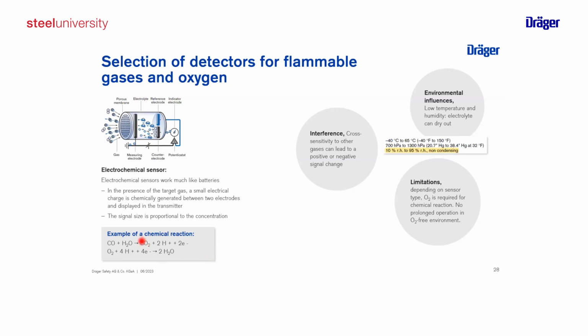I mentioned we also have some water inside, so liquid. So we need a certain environmental condition for the sensors so that they can operate. What we typically specify is 5 to 10% relative humidity as a minimum. Otherwise, the humidity from the inside will vaporize to the outside, so the sensor will dry out, and the electrons can't be generated or can't move through the electrolyte because there's nothing left. So you see, electrochemistry is quite simple in the idea behind it, but you have physical or environmental effects which can influence the performance of your sensor. So you need to keep in mind how and where you want to use these sensors.